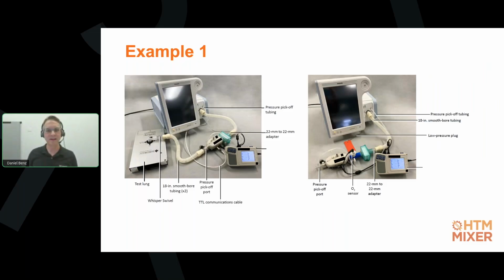So here on this picture, you can see an example for that. Here you can see 2 measurement setup pictures from a service manual of a ventilator manufacturer. Maybe some of you will recognize the ventilator here. The setup pictures themselves are actually pretty good, even though, for example, this teed-in pressure you can see here on this module here is kind of hard to see, right?